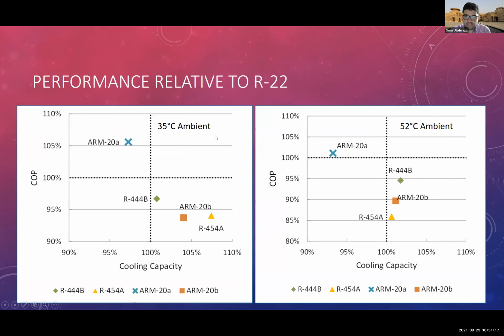You can see that at 35-degree ambient conditions, the only one that has higher COP is Arkema 20A. On the other hand, higher capacity is with R454A and Arkema 20B. When you go to higher temperatures, like 52 degrees ambient temperature, again, you can have higher efficiency and higher capacity on this end. Again, with proper engineering, you can match that of the baseline refrigerant, because the difference between the baseline and the alternative refrigerant is not that big, especially with R-444B. We are talking about 5% lower COP and slightly higher capacity. So this can be matched.